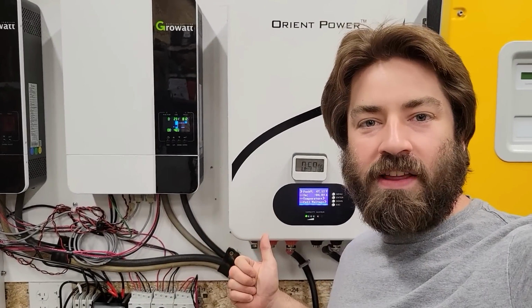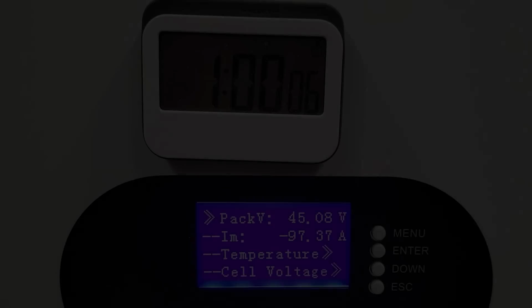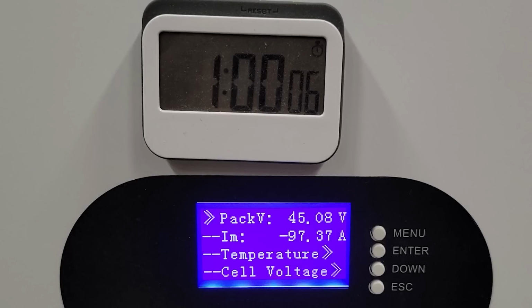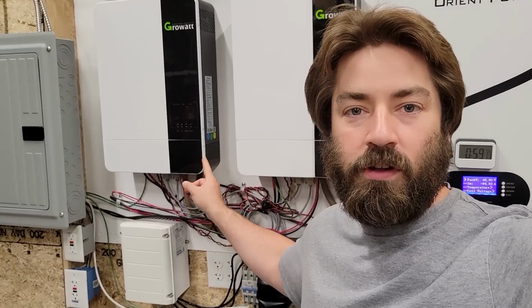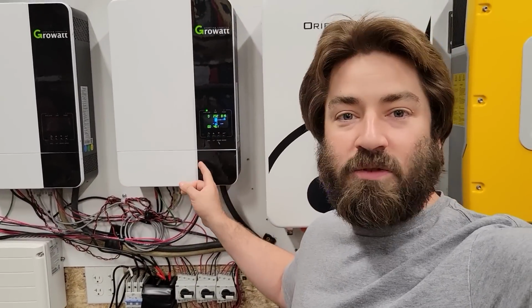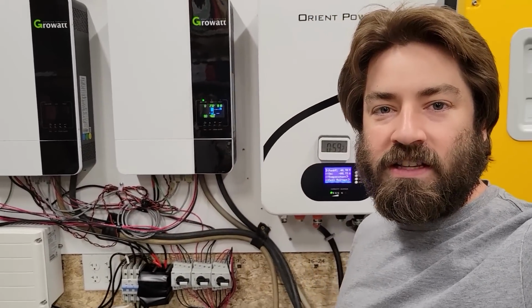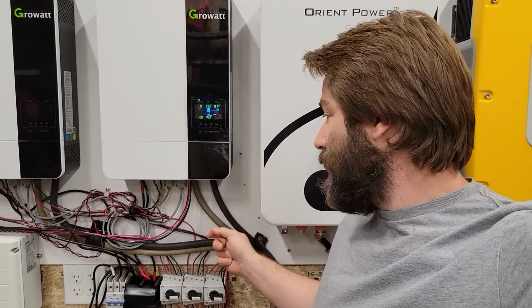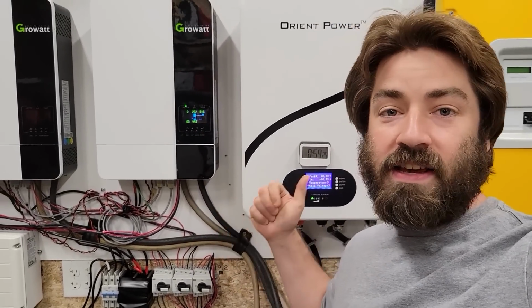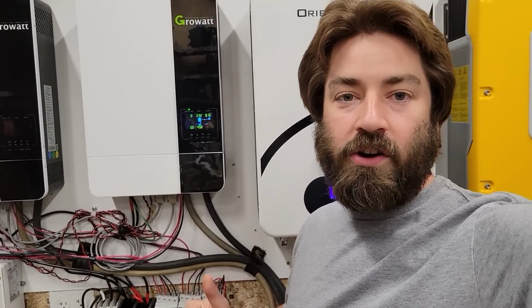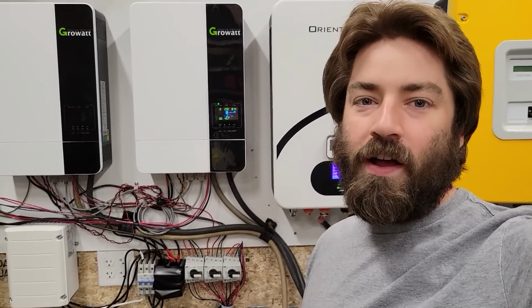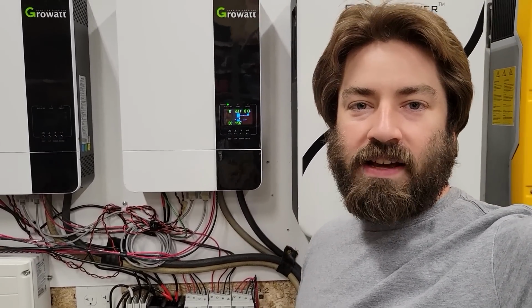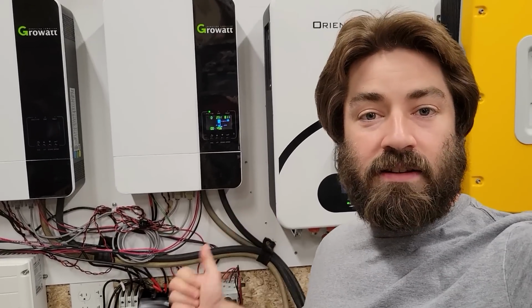I just finished running this battery for an hour around 93 to 94 amps, and it did not shut off. In fact, this inverter has shut off due to low voltage, and this other one is trying to keep up right now, it's about to shut off. So it's a success, it can do the 100 amps, it just can't go over it, not even for a second. But that's what we expect of these, and I'd say it was a success.